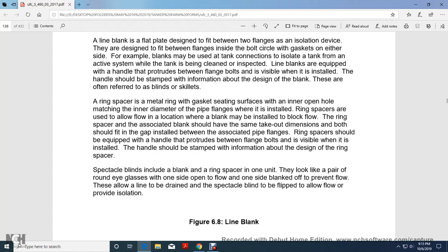A ring spacer is a metal ring with a gasket seating surface and an inner open hole matching the inner diameter of the piping flange. It is installed in the location of the blank when flow is required, and the ring spacer associated with the blank should have the same takeout dimensions. Both of them should fit with a gap between the associated pipe flanges. The ring spacer should be equipped with a handle that protrudes between the flange bolts, visible when installed, and stamped with the design information.